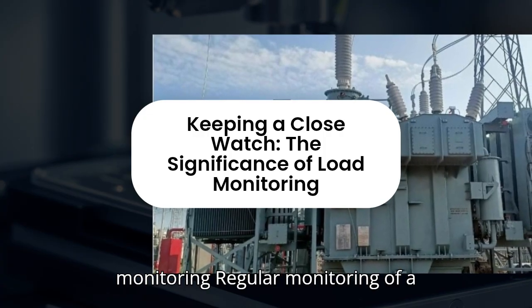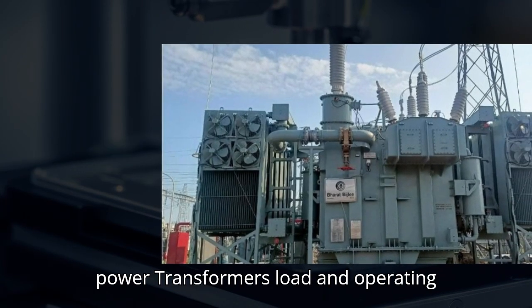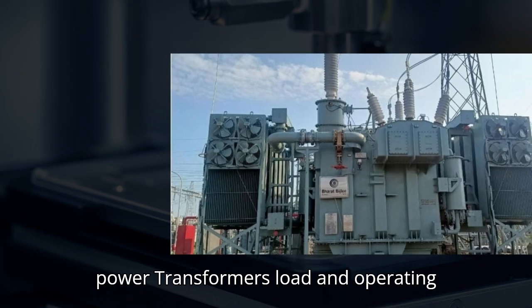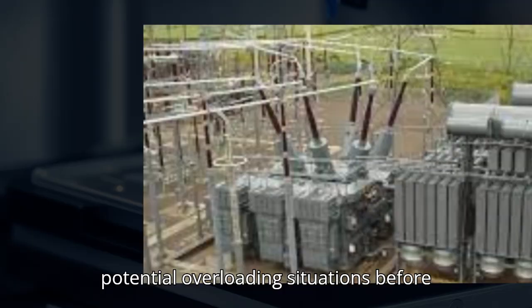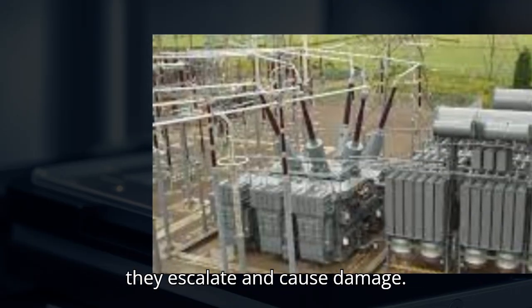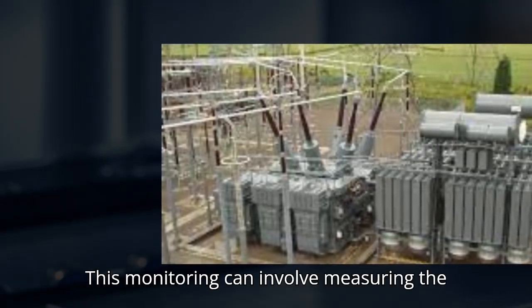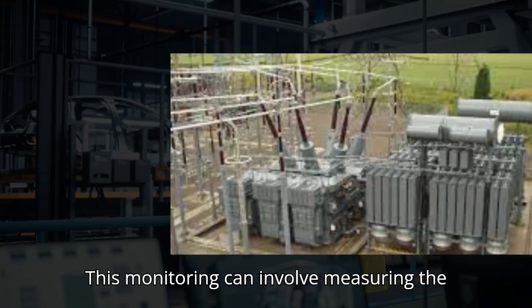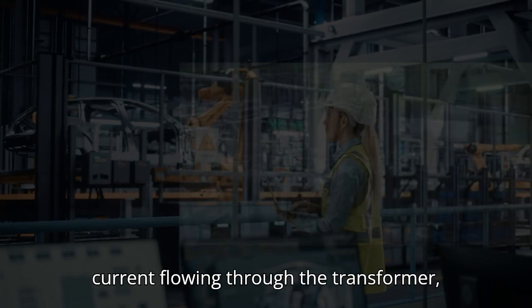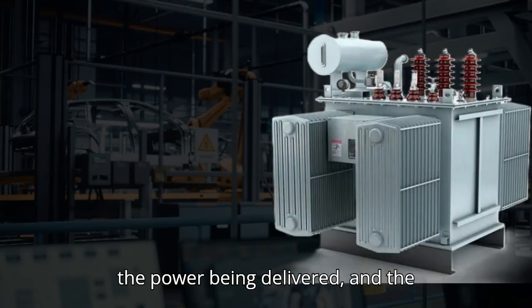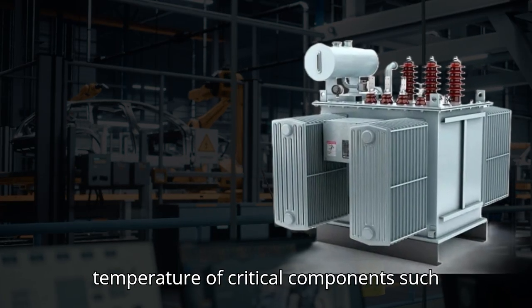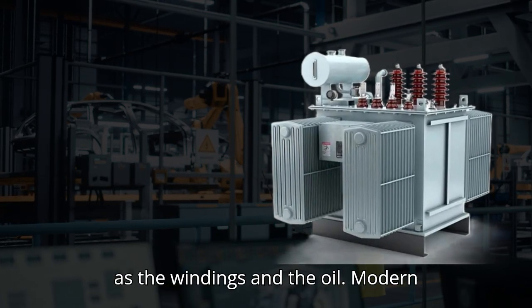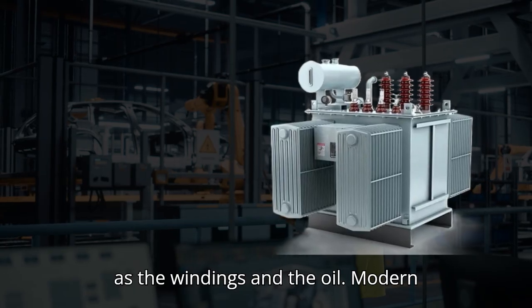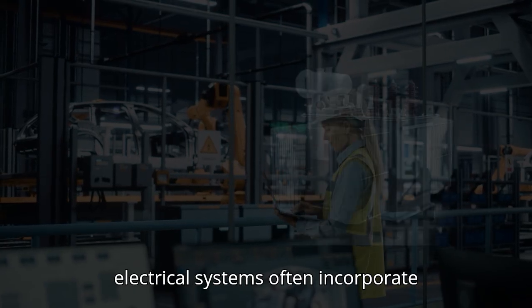Keeping a close watch. The significance of load monitoring. Regular monitoring of a power transformer's load and operating temperature is essential for detecting potential overloading situations before they escalate and cause damage. This monitoring can involve measuring the current flowing through the transformer, the power being delivered, and the temperature of critical components such as the windings and the oil.